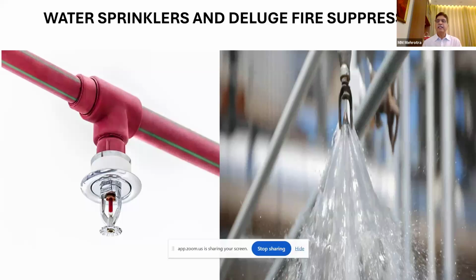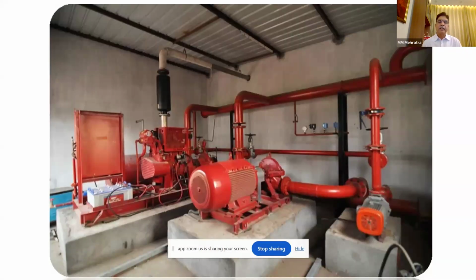So what will happen? This deluge fire suppression system will operate instantaneously, activated directly from the fire. It will not wait for the signal to come from the fire alarm system. Now what is there in my firefighting pump house? A firefighting pump house will always have three pumps. One is an electric driven pump, another is a diesel driven pump, and the third is a jockey pump. Now the electric driven pump is normally used for firefighting, but it may happen that when there is a fire, power supply to the building has gone. So if this is not there, it will wait for a certain time, and after that time it will operate. So it will ensure that water pressure of about 5 kg per centimeter square is maintained in the fire line.